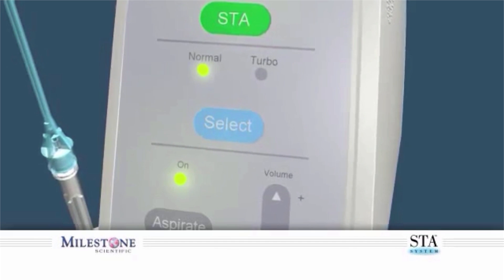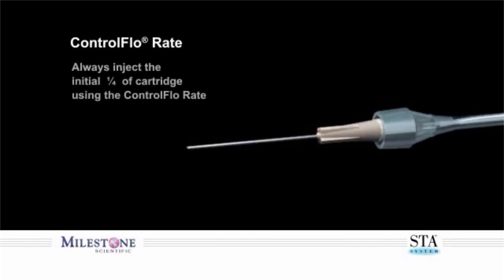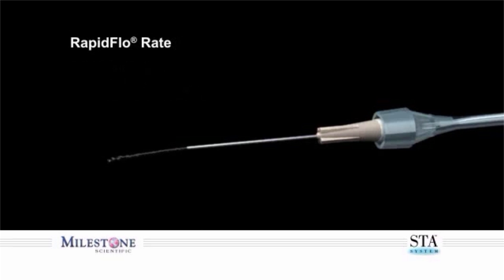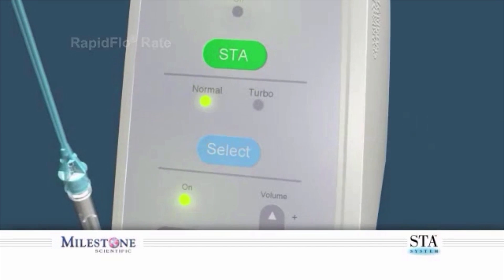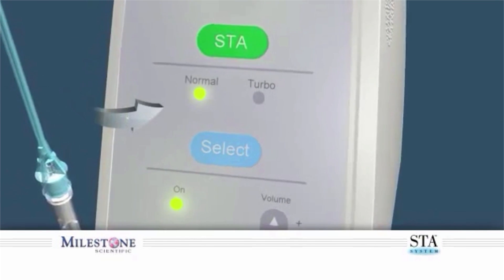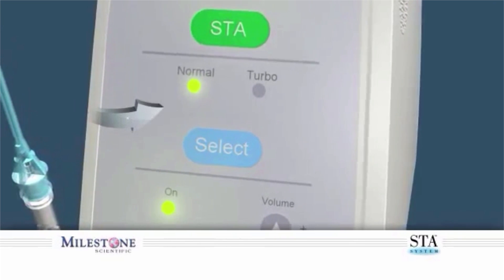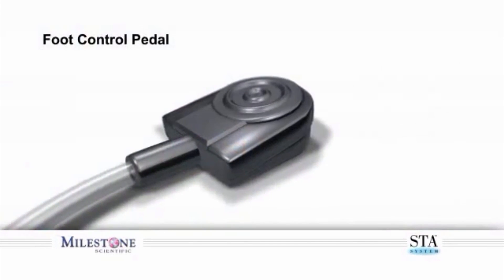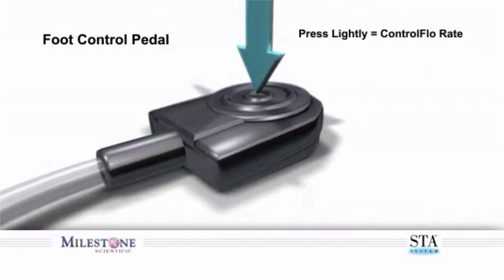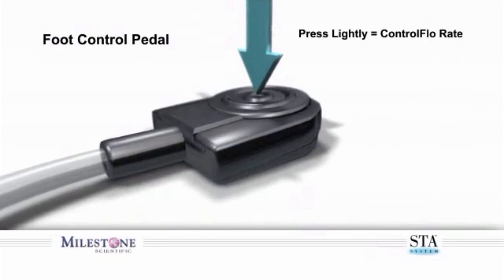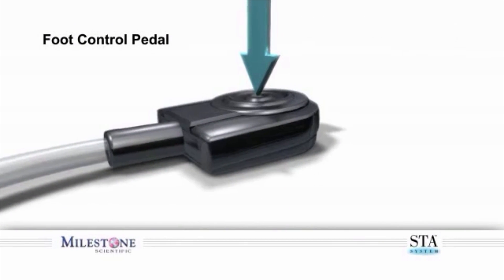Utilize the controlled flow rate to administer a minimum of one-quarter of the cartridge for the initial phase of the block injection. Once the patient feels the onset of soft tissue anesthesia, transition to the rapid flow rate. In the normal mode, the foot control has two distinct positions: depressing lightly enters the controlled flow rate; fully depressing enters the rapid flow rate.